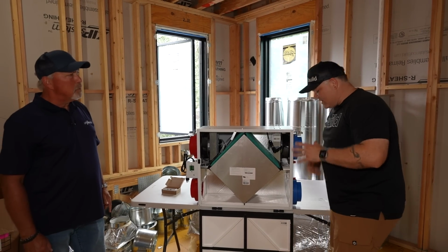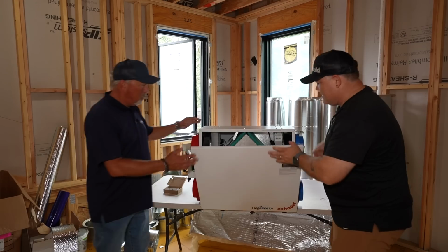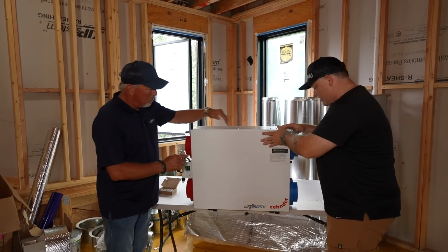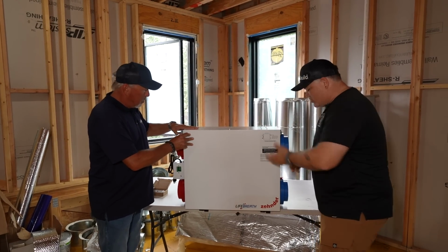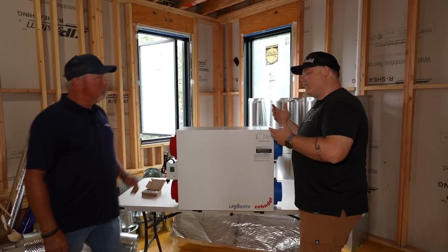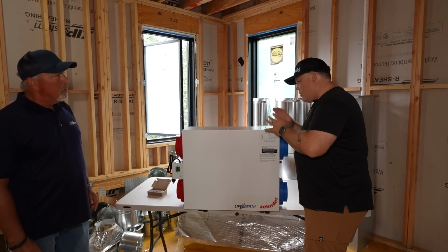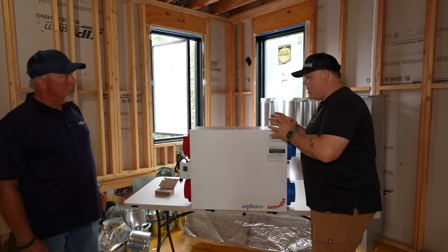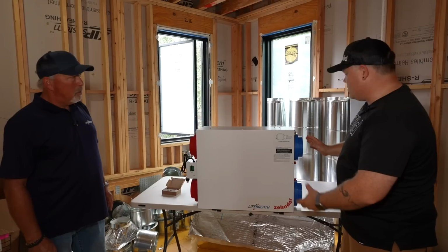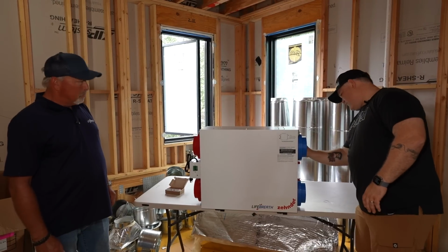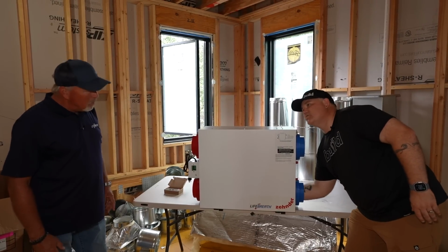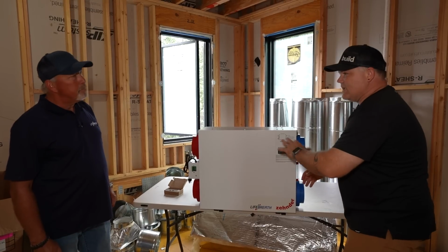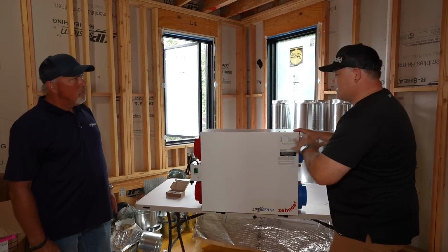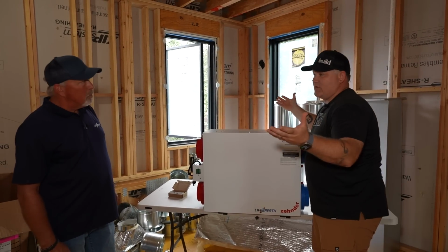Now that interests me, because when this is closed up you've got this nice insulated enclosure here. You've got no drain for humidity, for removing water or anything like that. How do you get the exact right amount of air when I don't see any dampers in here? There's a fan here, but I can put my hand right in there. There's no damper, where I'm used to seeing a damper for balancing.